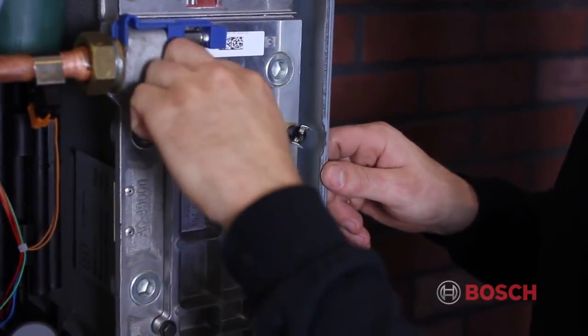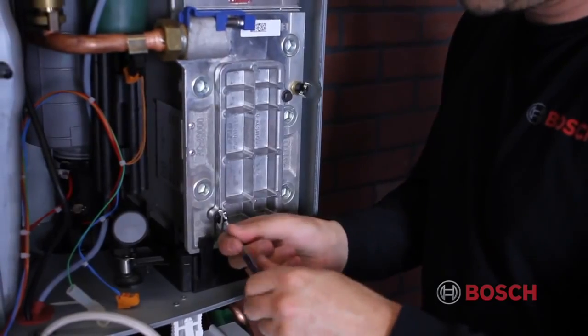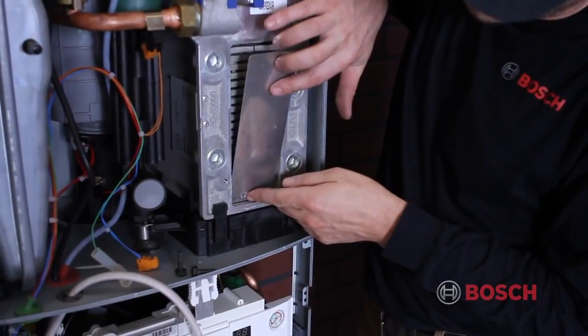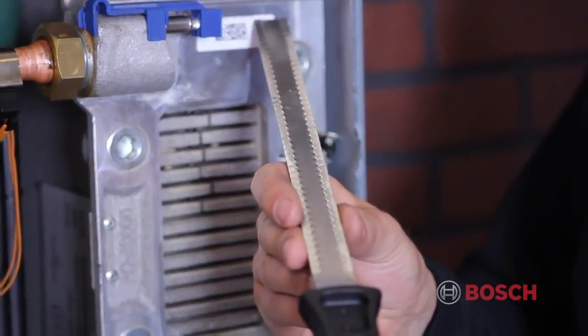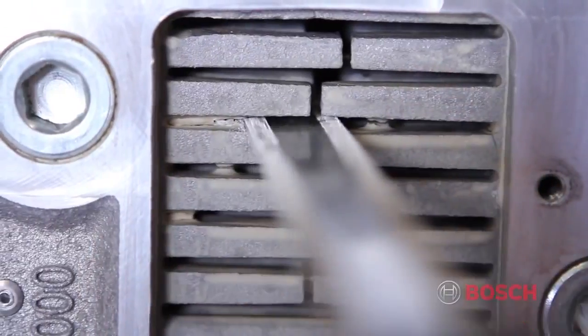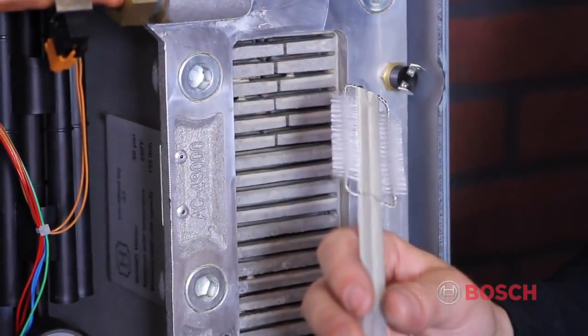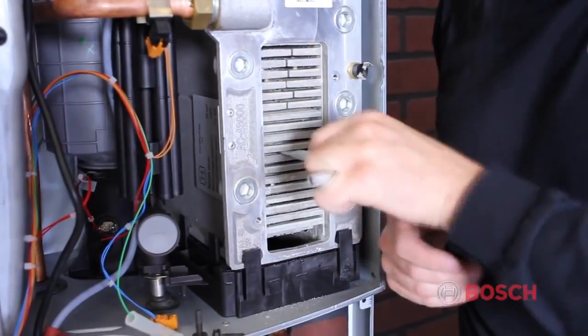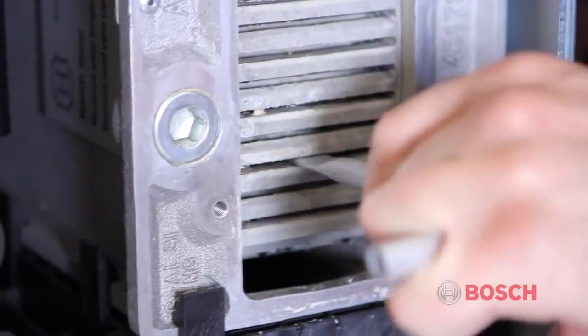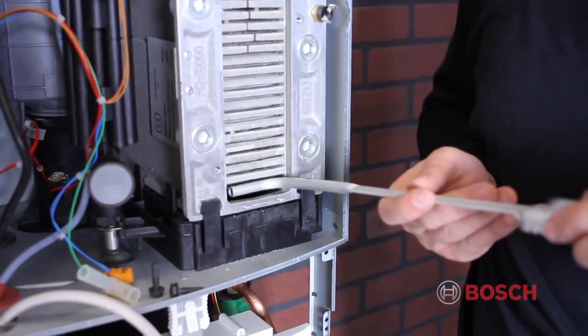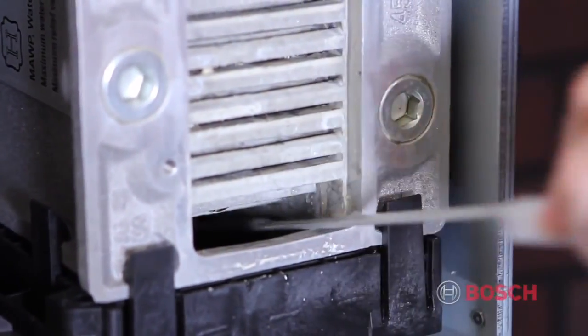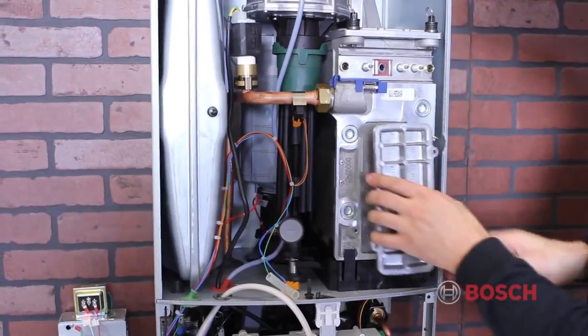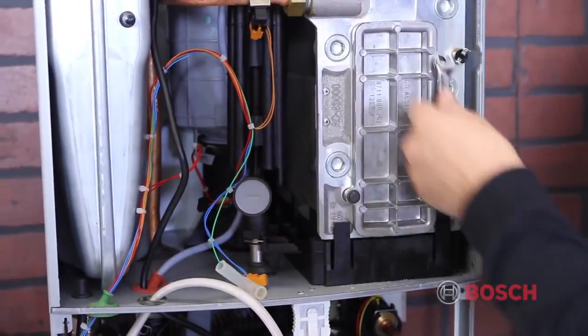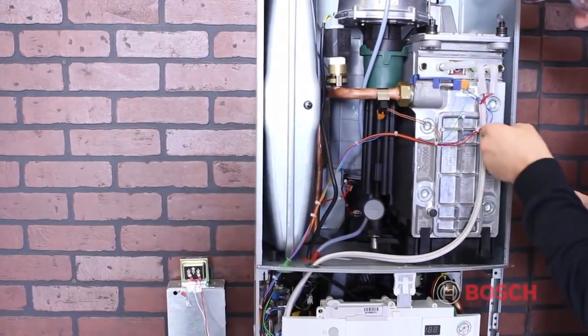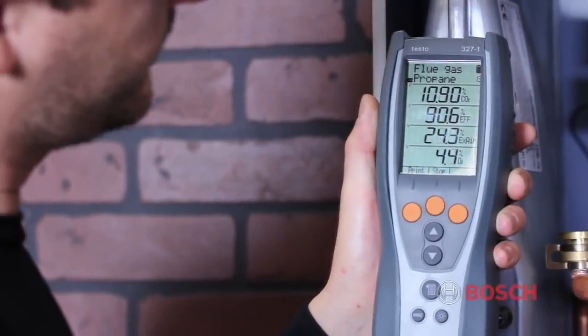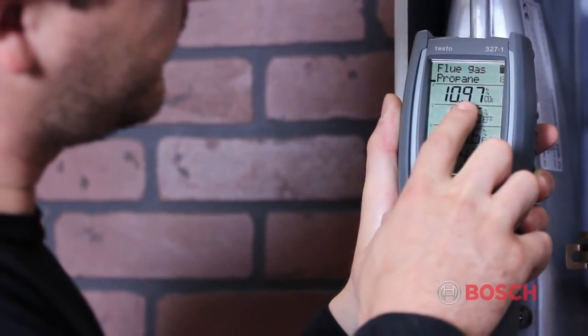Remove the 2 10mm nuts that hold the access plate in place. Then remove the access plate and the heat shield. With a cleaning blade, clean the heat exchanger block from the bottom to the top. And then with a brush, clean from the top to the bottom. Rinse the heat exchanger with water from the top. Clean the condensate tray and then reassemble the heat exchanger by installing the heat shield and the access panel. Note, always install a new gasket after cleaning the heat exchanger. After cleaning the heat exchanger, perform a combustion test to verify the performance of the appliance.